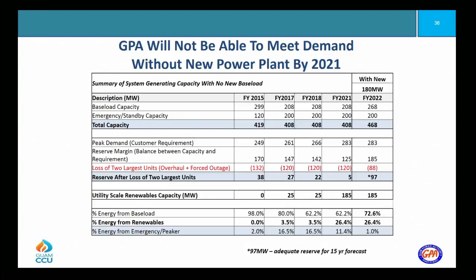We will not be able to meet demand without a new power plant, as can be seen here. We have 419 megawatts today. We take 249 out, in 2015. We only had 170. Minimum contingency is at least the two largest units, which is 132, so we only had about 38 megawatts over and above that reserve margin.